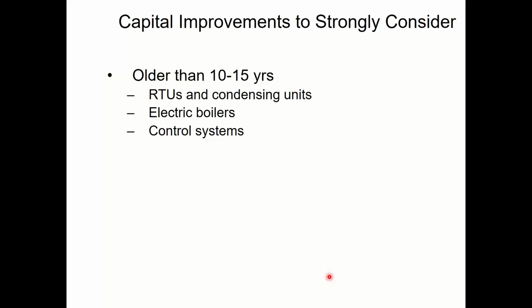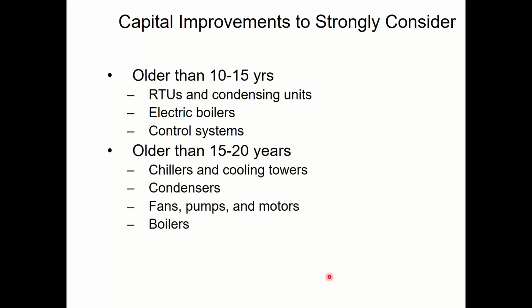I'm looking to get that thing off the roof at that point and get something else on there. So when you get to that age, I would only do the maintenance things and I wouldn't invest in anything new. And I would start my planning process for replacing the entire unit. So rooftops and condensing units at 10 to 15 year range. If I have control systems, by year 10, they're pretty obsolete. That industry changes so fast, and there's so many things that can save energy there that upgrading the controls every 10 years is pretty desirable.